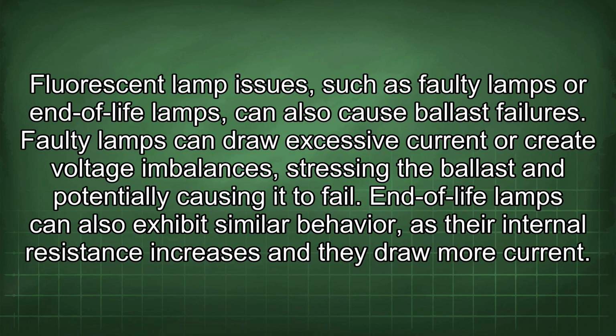Fluorescent lamp issues, such as faulty lamps or end-of-life lamps, can also cause ballast failures. Faulty lamps can draw excessive current or create voltage imbalances, stressing the ballast and potentially causing it to fail. End-of-life lamps can also exhibit similar behavior, as their internal resistance increases and they draw more current.